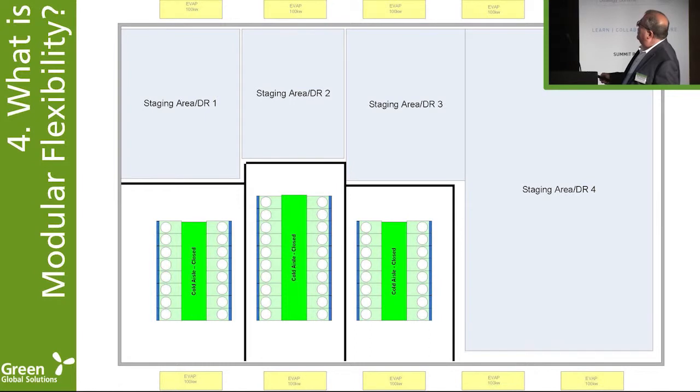There we go. Just imagine if we had first customer, say this is a co-location facility, first customer says, okay, I got 20 racks. So you fill up with 20 racks. Well, do we have to have everything all switched on? No, it'd be pretty expensive if we did that, wouldn't it? So what we do here is we run a set of baffles under the floor here across to there. So the air that comes from here is only going to sit under here. No leakage. We'll have silicon. We'll block off any leakage area. And so therefore, this is the only area that will cop the air.